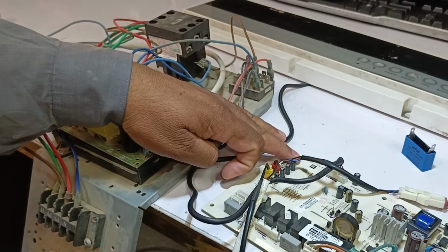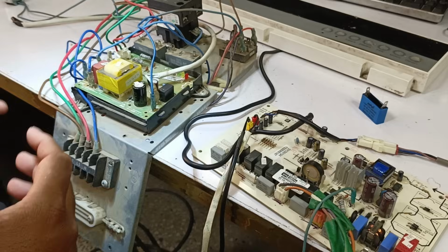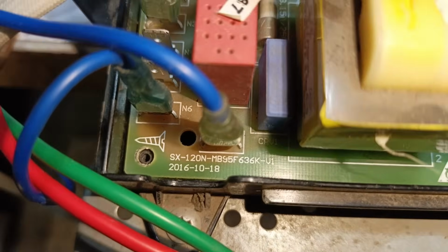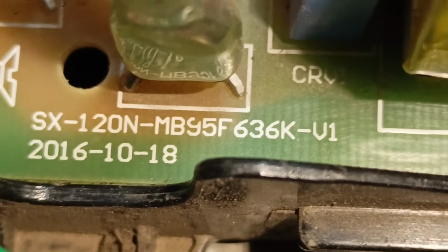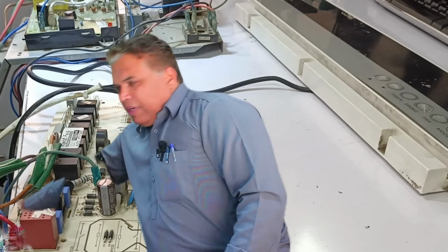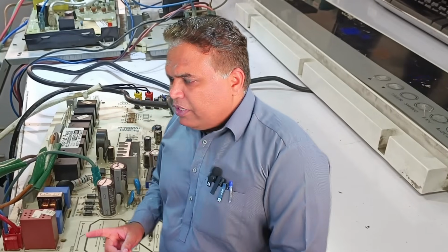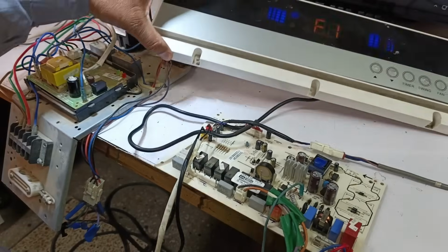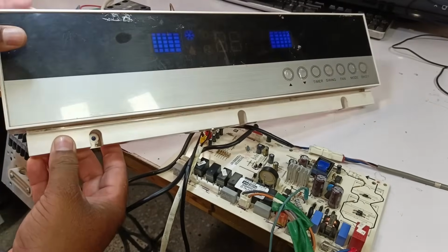The model number of the indoor circuit board is written here. Similarly, the outdoor circuit board also has its model number written here, which you are able to see. Now, let me show you what the problem is in this circuit. I am now turning on the indoor unit and supplying power to it. As soon as I turn it on, the display shows a temperature of 16 degrees Celsius, and at the same time, an F1 error is also appearing on the display.